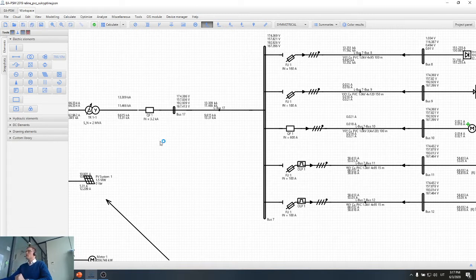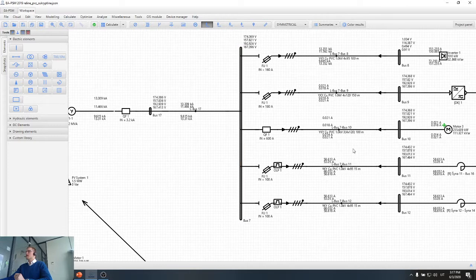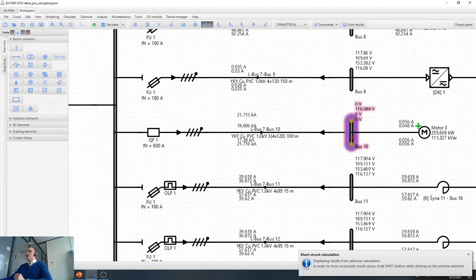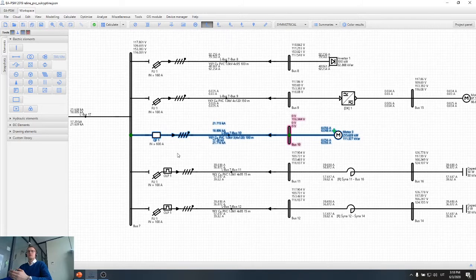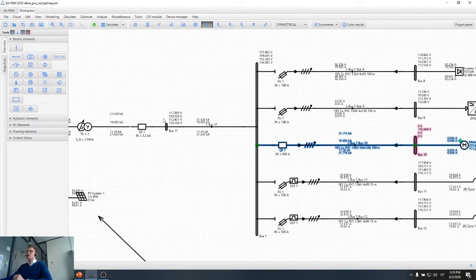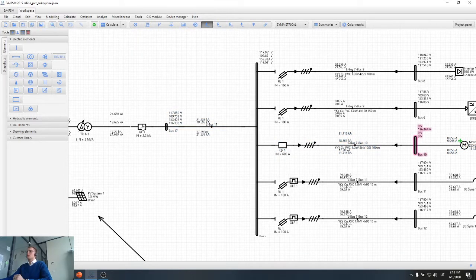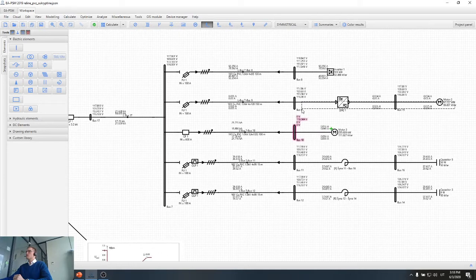And lastly, but also very important, the last feature of protection devices is selectivity. So what does selectivity mean? Again, let's take the same line as an example. If I have a short circuit in bus 10 or in my motor, I want only this line to be disconnected. Because if protection devices don't work selectively, what will happen? For example, it might happen that the incomer protection device, this breaker, will disconnect, and basically all the other motors, protection coordination, also reactive power compensation devices, inverters, all the loads will be disconnected from the network. And in the best case scenario, only this protection device should have been disconnected.